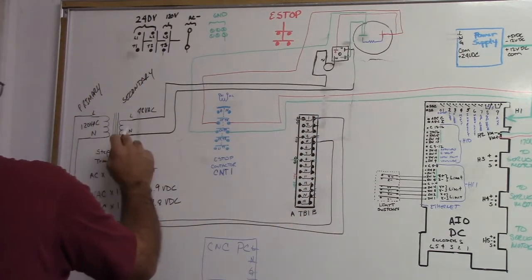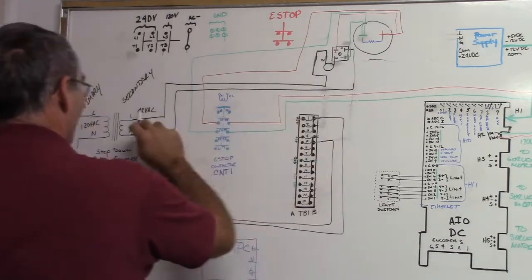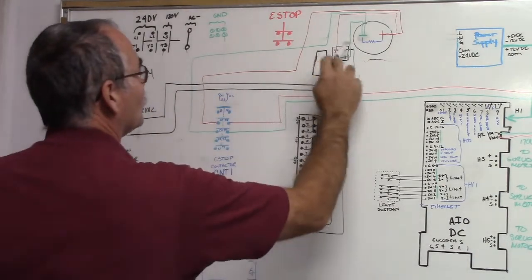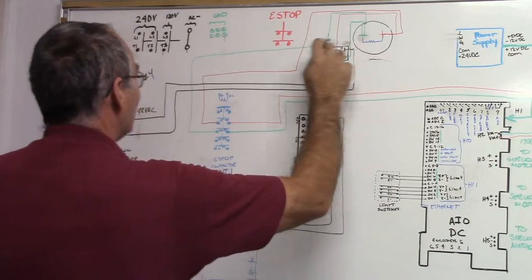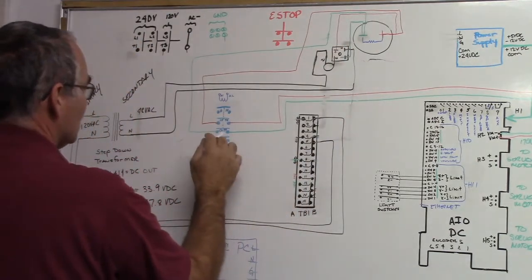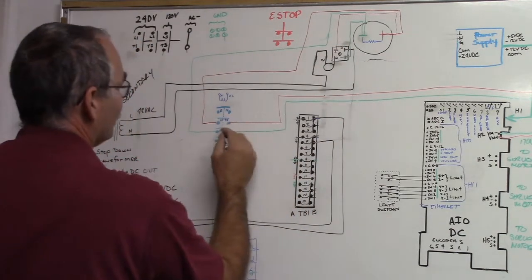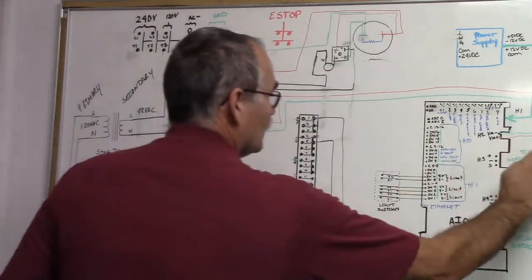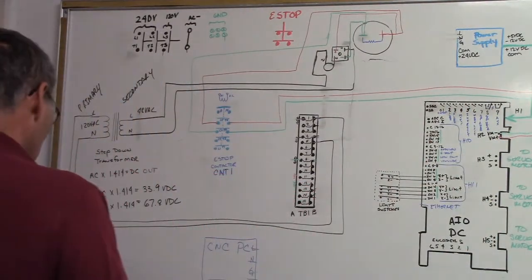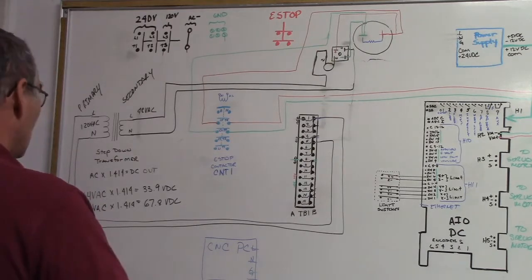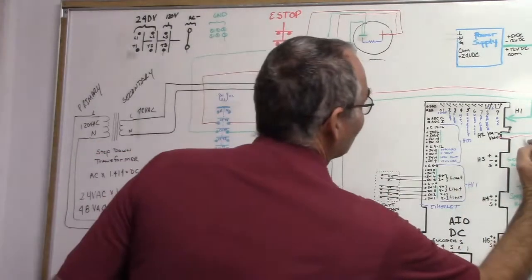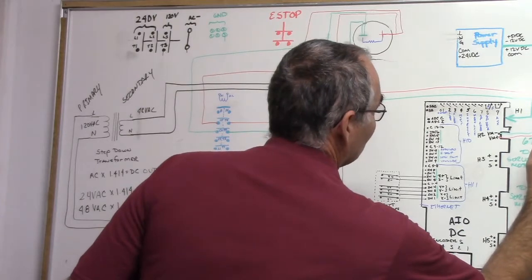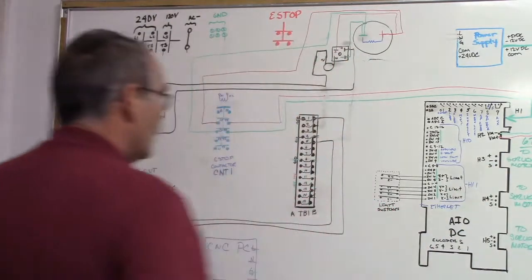Now we got voltage out, 48 volts AC out, goes through our bridge, goes through our cap, and then it comes over to our CNT1 contactor, L3 and L4. And now what do we have over here? We don't have 170 volts over there. What do we have over there? We've got 67.8 VDC.